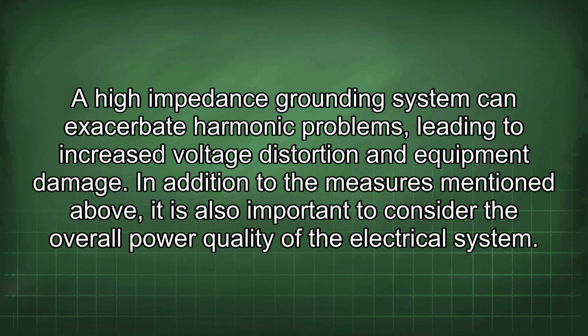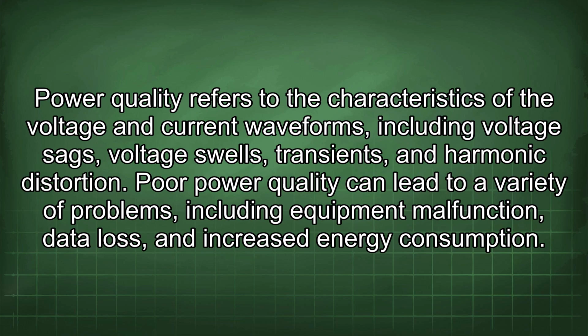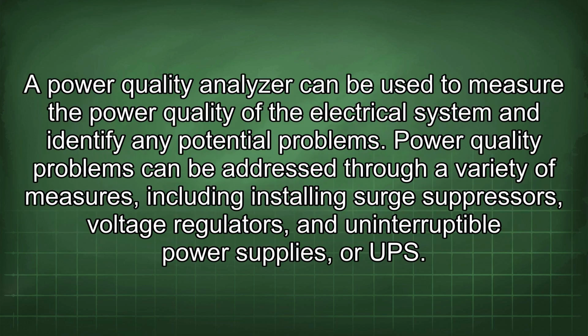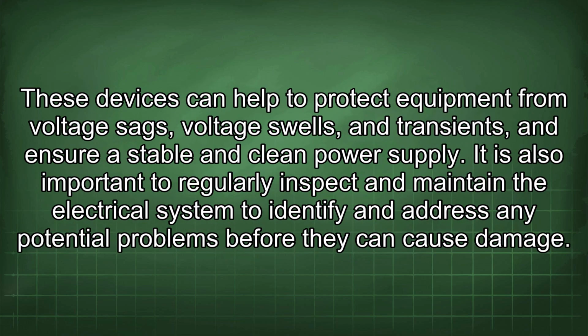In addition to the measures mentioned above, it is also important to consider the overall power quality of the electrical system. Power quality refers to the characteristics of the voltage and current waveforms, including voltage sags, voltage swells, transients, and harmonic distortion. Poor power quality can lead to a variety of problems, including equipment malfunction, data loss, and increased energy consumption. A power quality analyzer can be used to measure the power quality of the electrical system and identify any potential problems. Power quality problems can be addressed through a variety of measures, including installing surge suppressors, voltage regulators, and uninterruptible power supplies, or UPS. These devices can help to protect equipment from voltage sags, voltage swells, and transients, and ensure a stable and clean power supply.